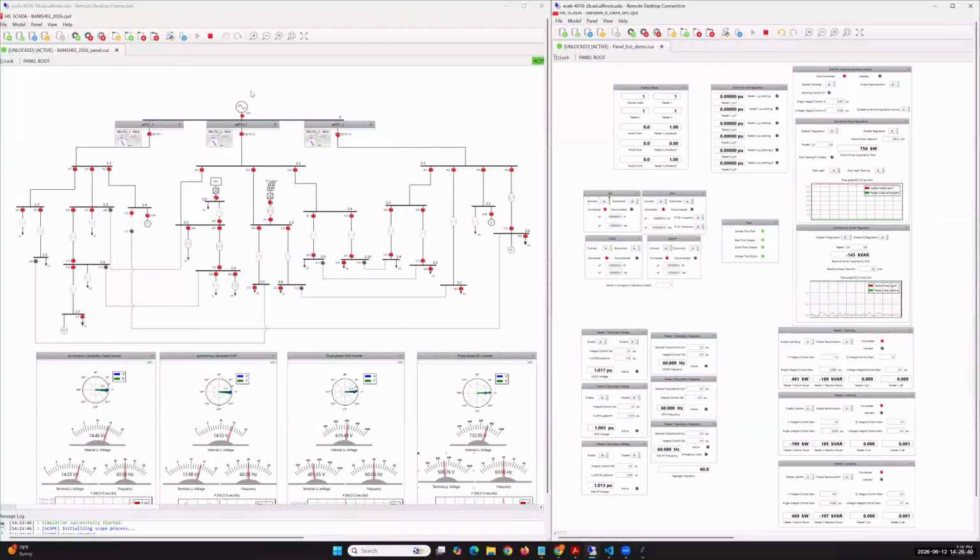So the first showcase of the distributed control is to island the microgrid from the main grid by driving the tie line power flow across the point of interconnection with the grid to 0. Once that is done successfully, we should have an islanded microgrid, all 3 feeders in one grid, and then we are going to turn on distributed frequency control for that islanded microgrid.